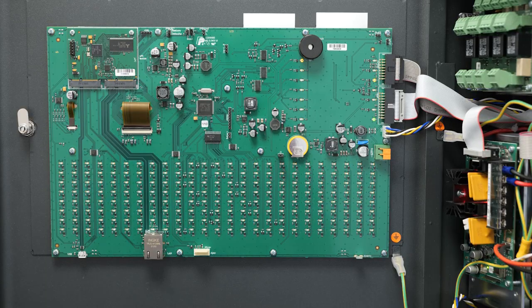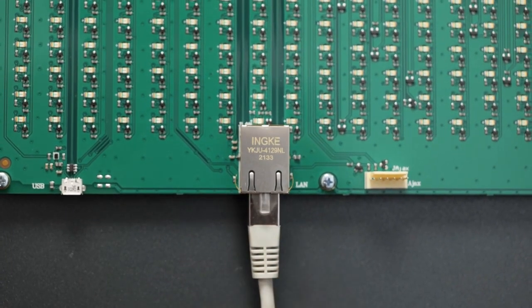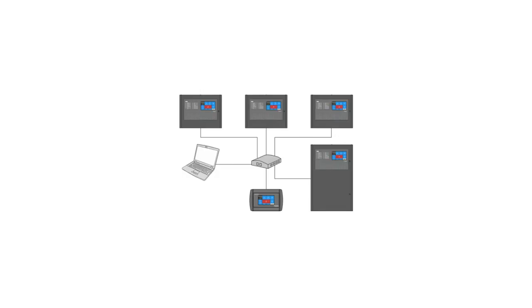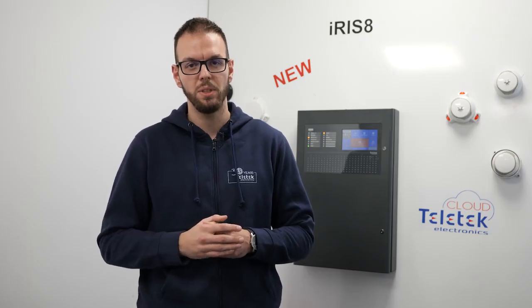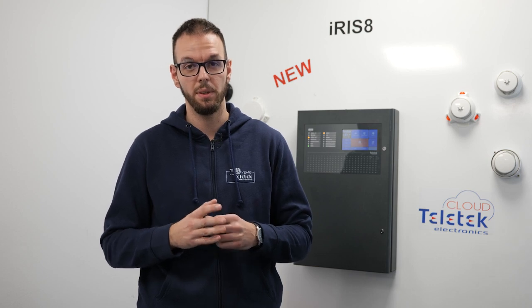As we mentioned earlier, we can use the built-in LAN module of the IRIS panels to create a network. We can use a standard CAT cable to connect the IRIS panel to the LAN network. We have 2 options: to connect the panels over the internet, where every panel is online and it is using a real IP and we are not limited in distance between the panels. Or we can make a direct connection between panels, but in this case we need to use switches on every 100 meters.